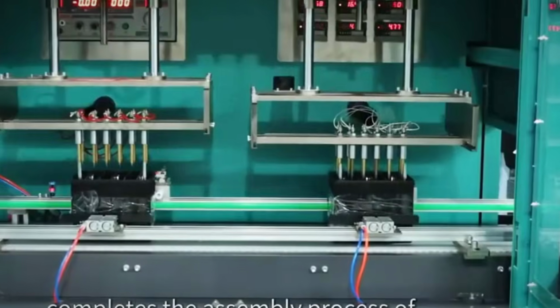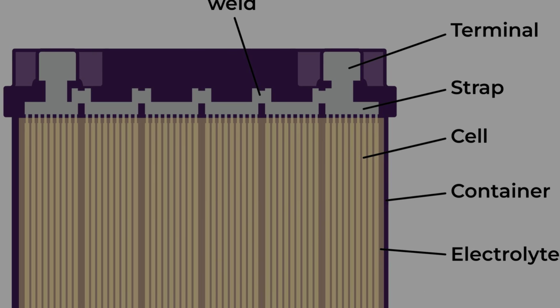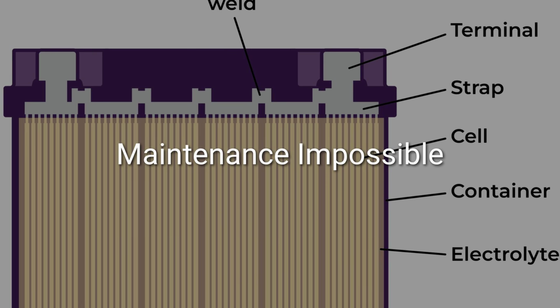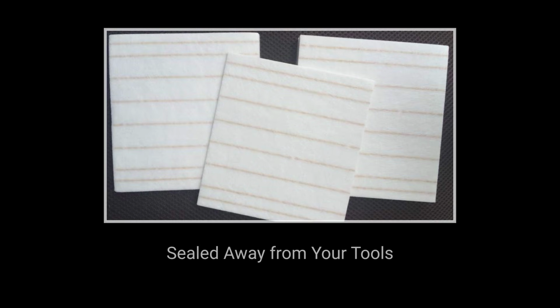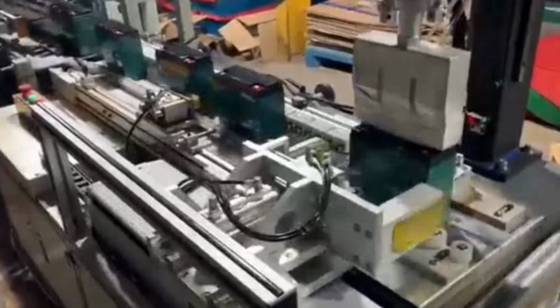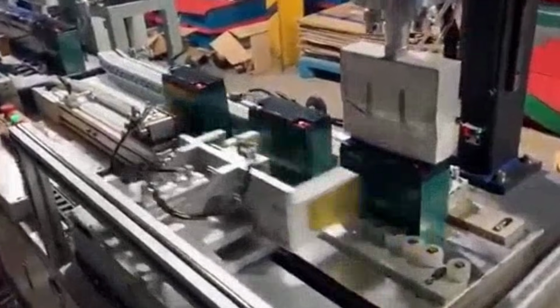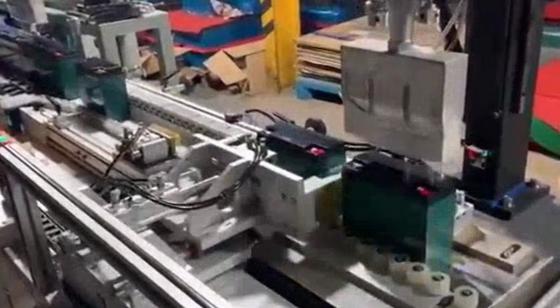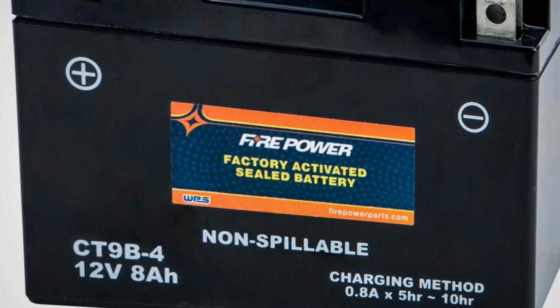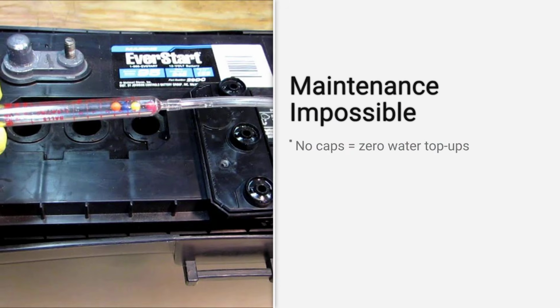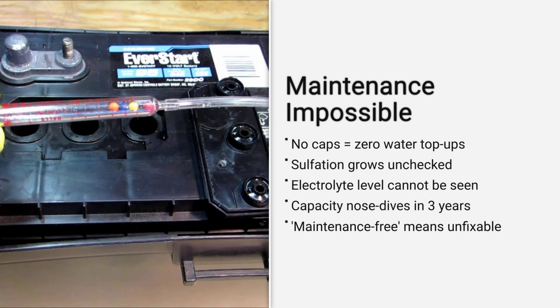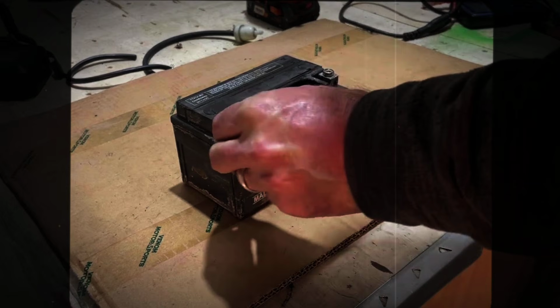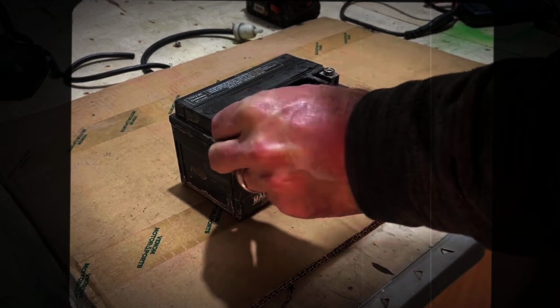Then the industry switched to sealed AGM batteries. AGM stands for absorbent glass mat, and instead of liquid electrolyte sloshing freely between the plates, the acid is absorbed into fiberglass mat separators sandwiched between them. The case is welded shut. There are no caps. There is no way to check the electrolyte level, no way to add distilled water, and no way to perform the one maintenance action that kept those older batteries alive for a decade.